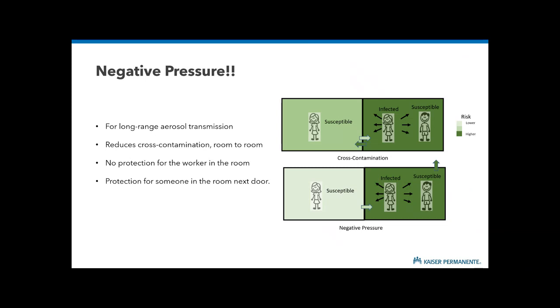Negative pressure does one thing and one thing only. It prevents cross-contamination of the room next door. So it is a tool to prevent long-range transmission. This should start to sound repetitive, but again, to date, COVID-19 has never traveled in the air to the room next door and caused an infection. So negative pressure is a protection against something that's never actually happened. It's not really even suspected of happening.